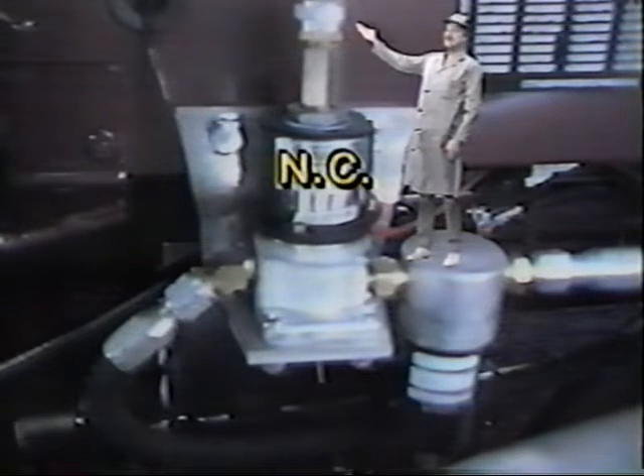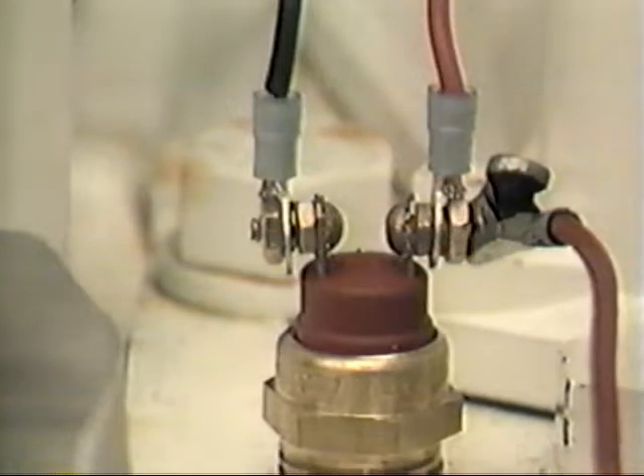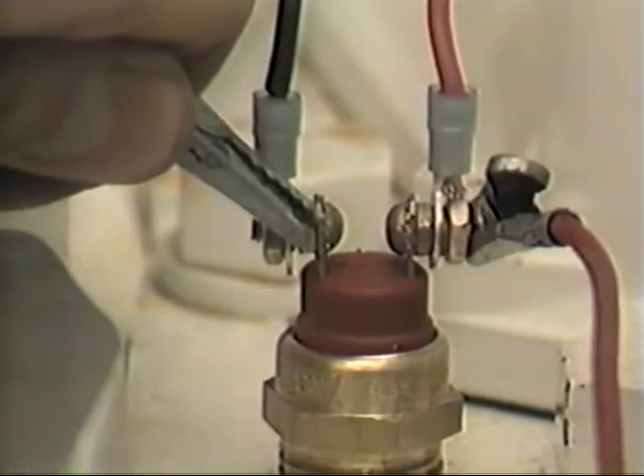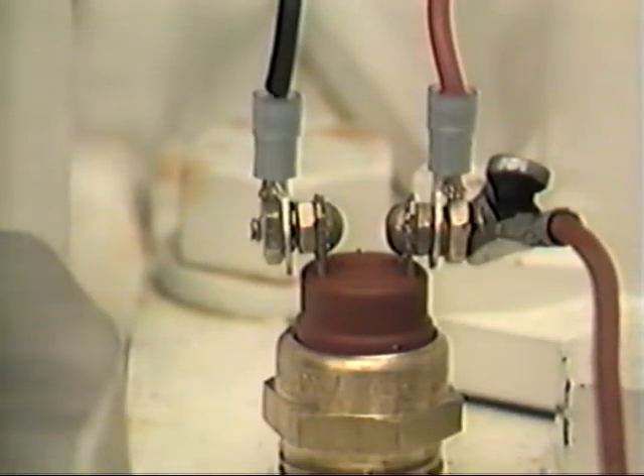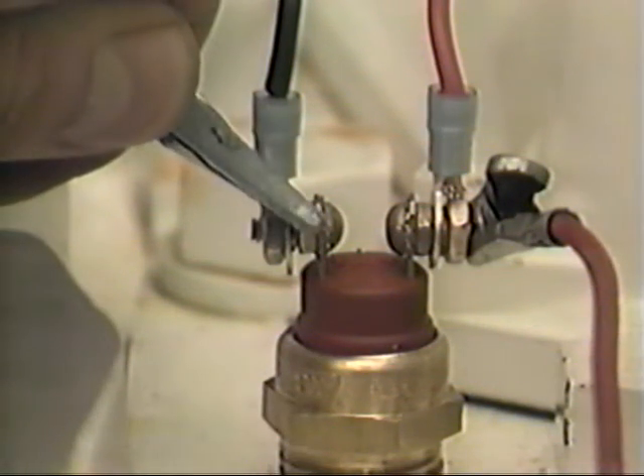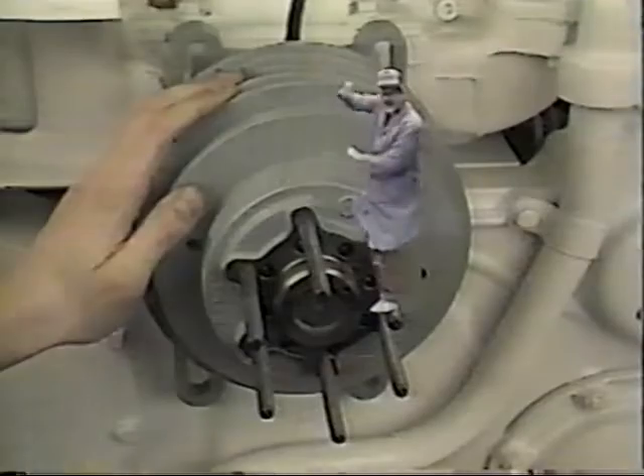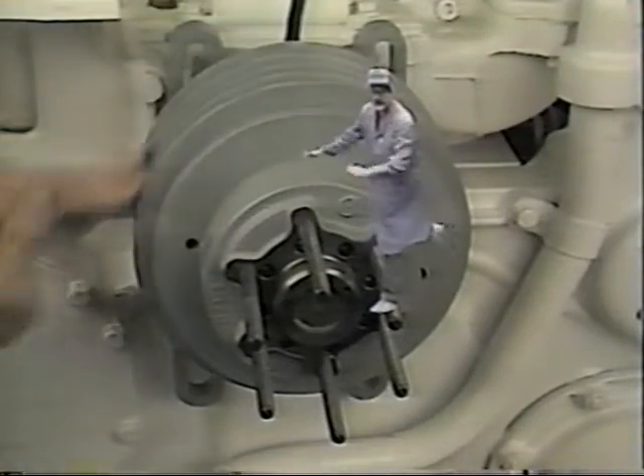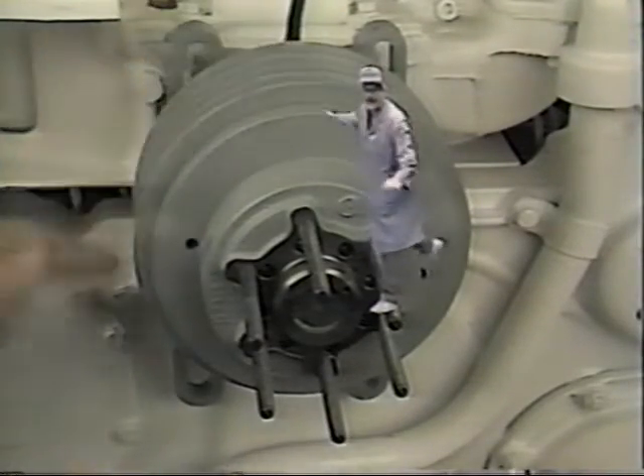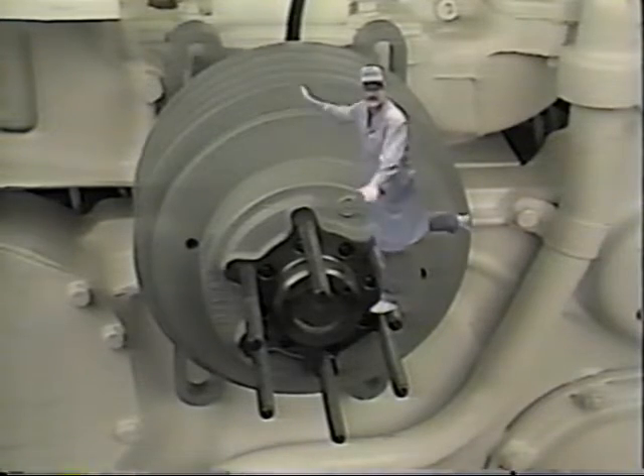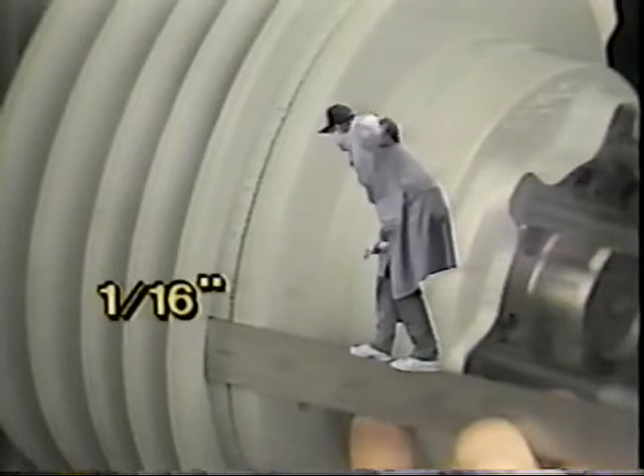With a normally closed valve, a jumper wire across the two thermal switch terminals should cause the fan clutch to engage and disengage. Repeat this 3 times. With the fan disengaged, rotate to see if there is any roughness in the sheave bearings. Check the lining and replace it if it's worn to 1/16 of an inch or less.